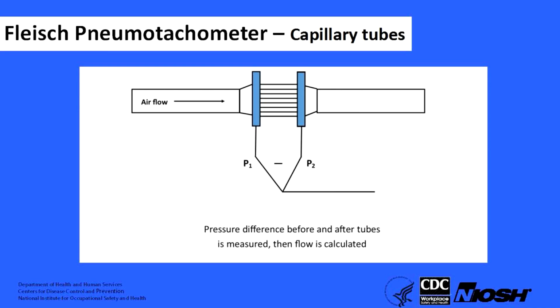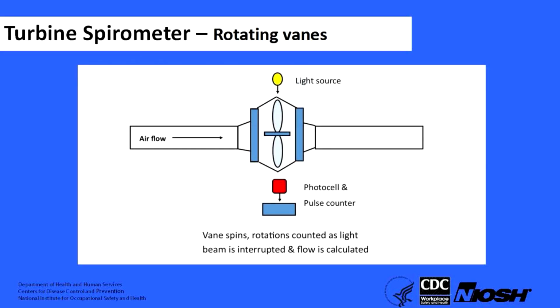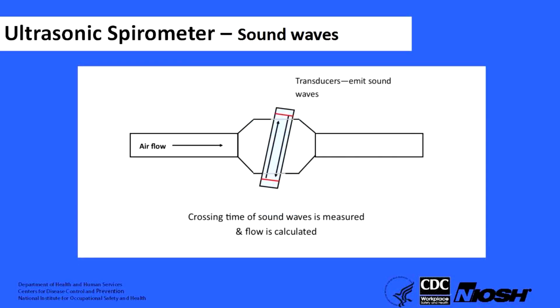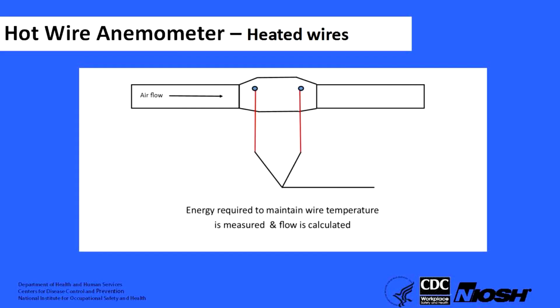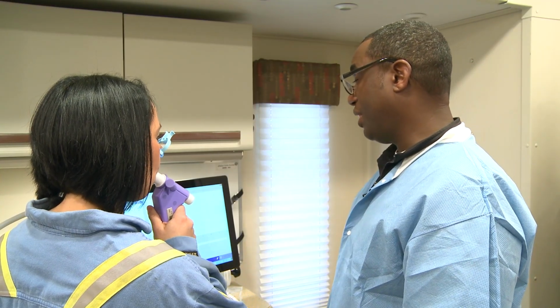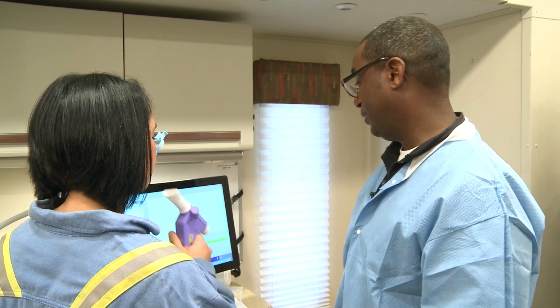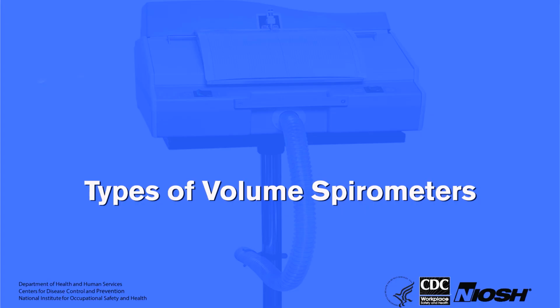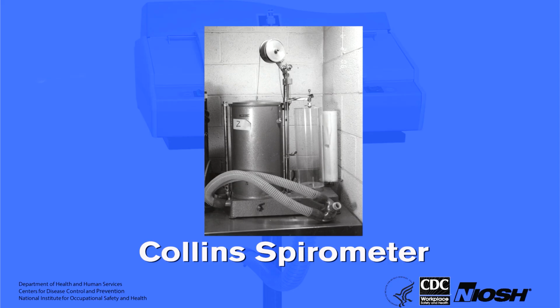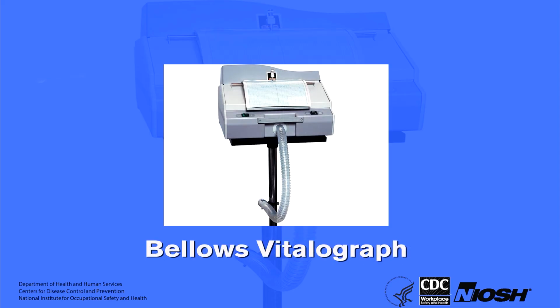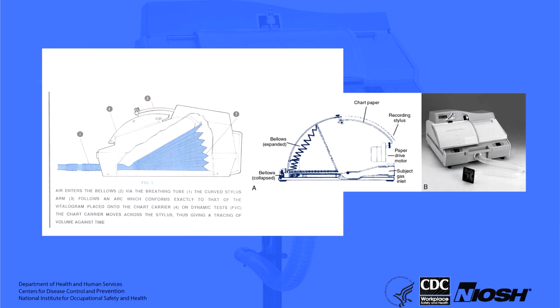Pneumotachometers measure pressure on both sides of a resistance element. Turbines count the number of vane rotations within the breathing circuit. Ultrasonic spirometers measure the time it takes a sound pulse to cross the breathing tube. Hot wire anemometers measure the electrical current needed to maintain a superheated wire at a constant temperature. Flow spirometers must be able to accurately measure a wide range of airflows. Volume spirometers use an earlier and simpler technology. Volume spirometers directly measure the amount of air exhaled and collect that air in a chamber. With the appropriate software, volume spirometers can display both volume time and flow volume graphics as recommended by the ATS-ERS guidelines.